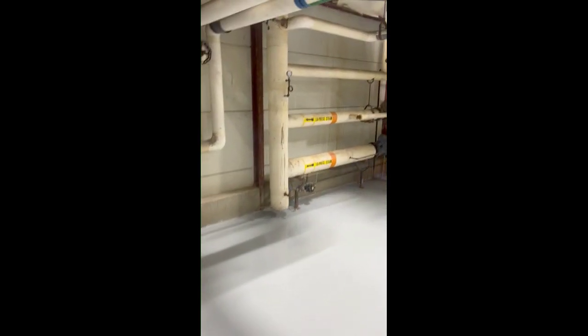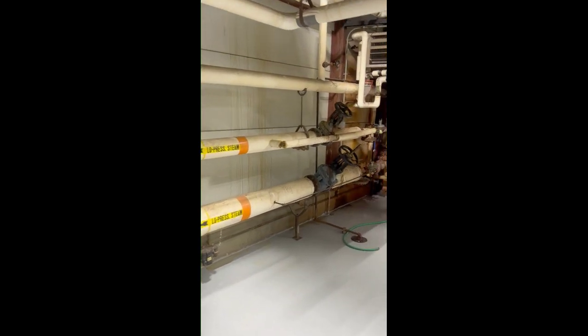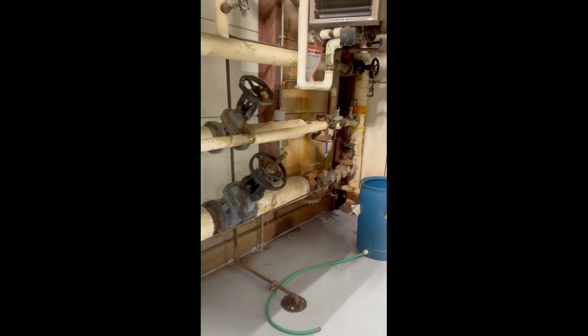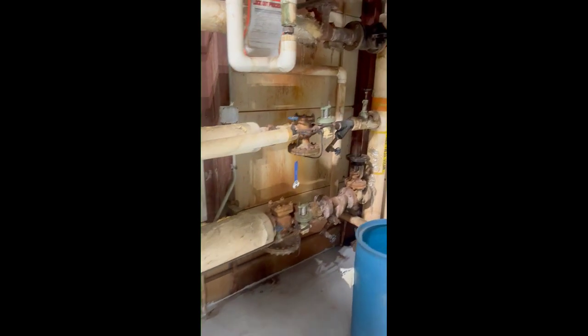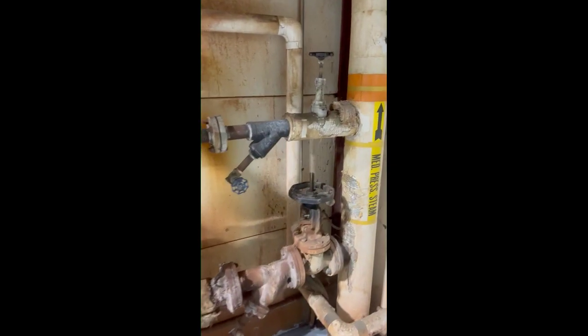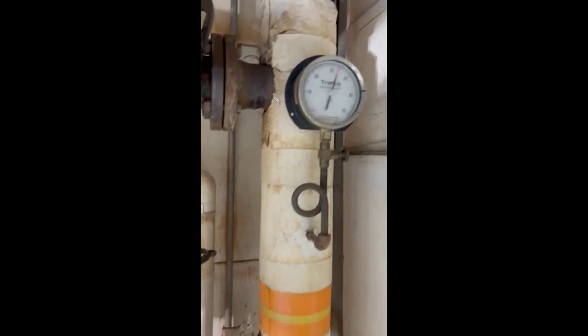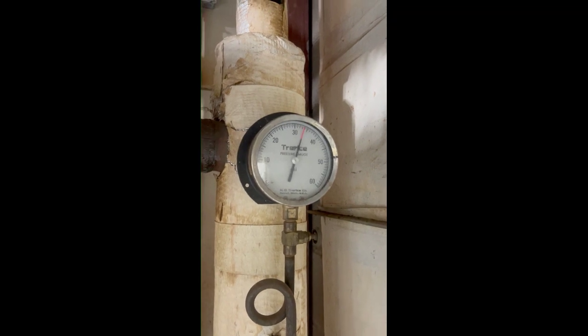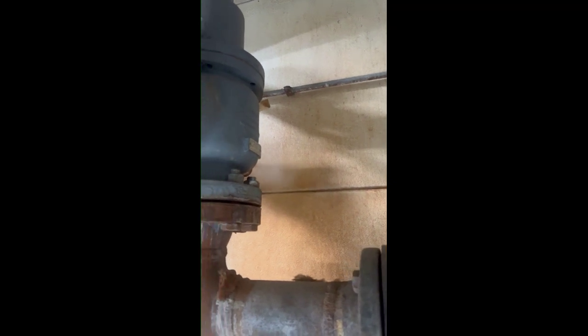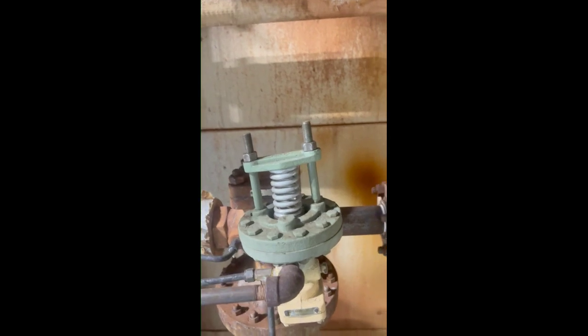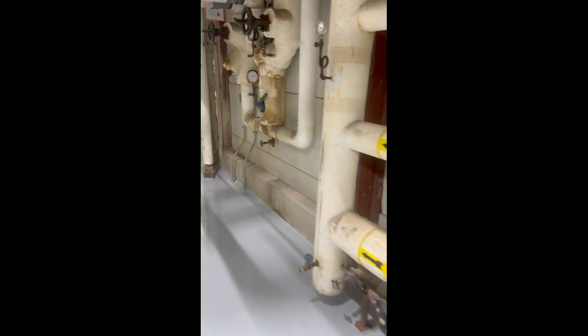Now I'm going to go to where we talked earlier about the boiler room, and that boiler providing medium to low pressure steam. I'm going to come up here to make sure that in my main steam manifold I have boiler pressure. And in this case I got plenty. I do have a pop-off valve right now that's blowing, so that's abnormal. I got to fix that. So I will adjust this valve down to make sure that this doesn't continue to happen.